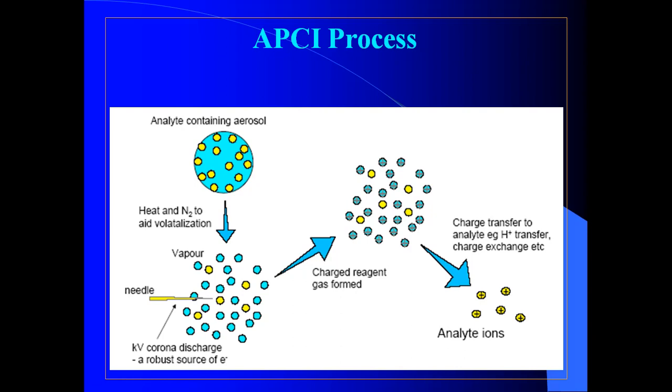The gaseous sample and solvent molecules are swept from the probe, and the second gas, you can see here the auxiliary gas, into the ion source, where ionization by APCI is induced by the corona discharge needle. The sample molecules are ionized by collision with the reagent ions created by ionization of mobile phase solvent molecules. And then these ions, the analyte cations, transfer to the mass analyzer.